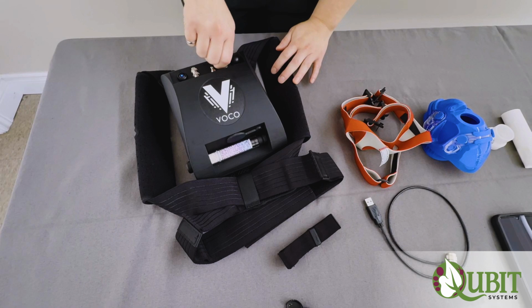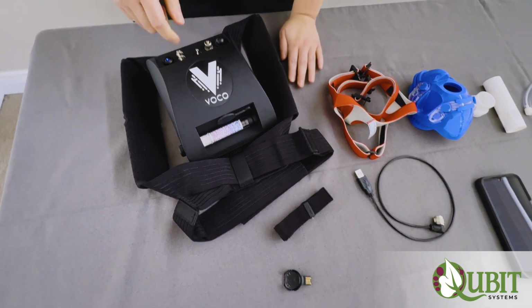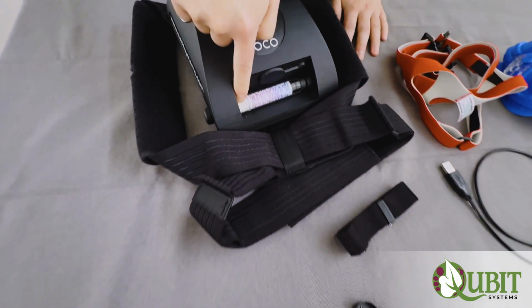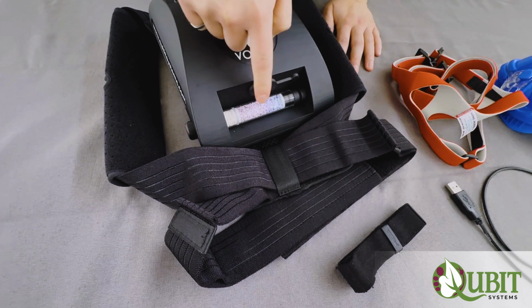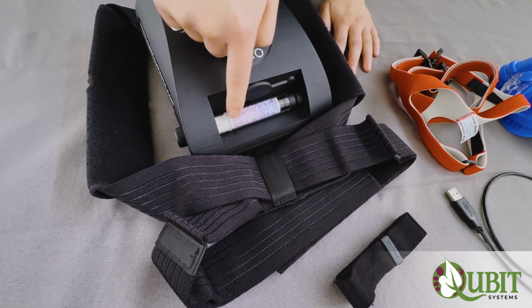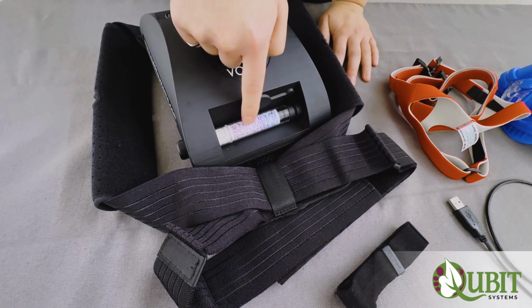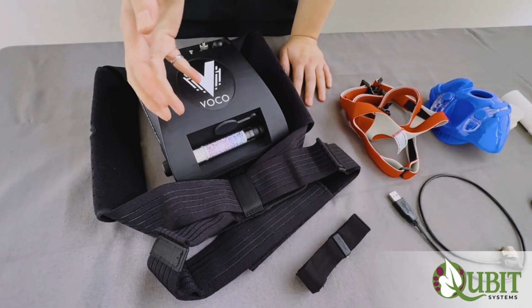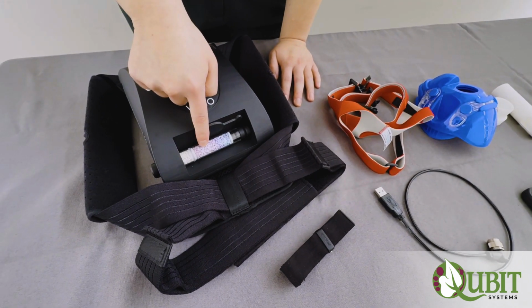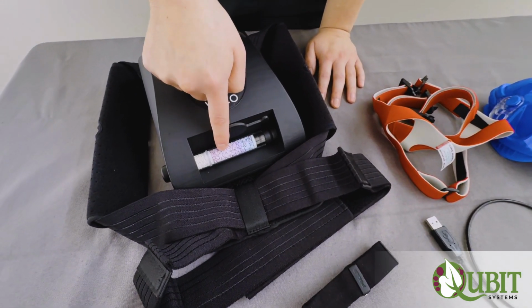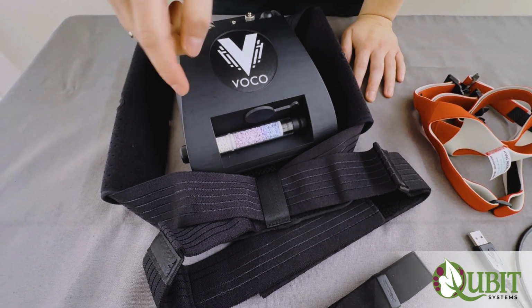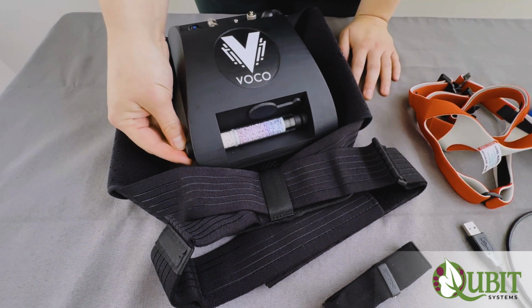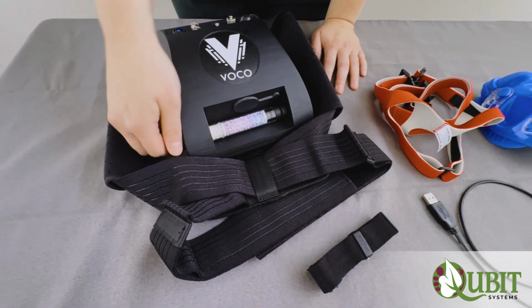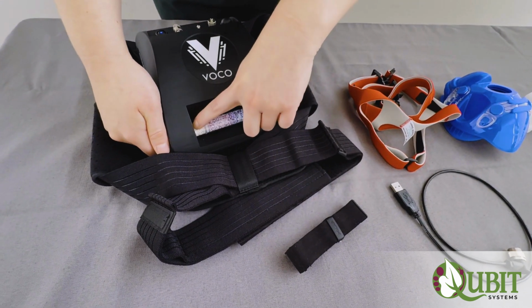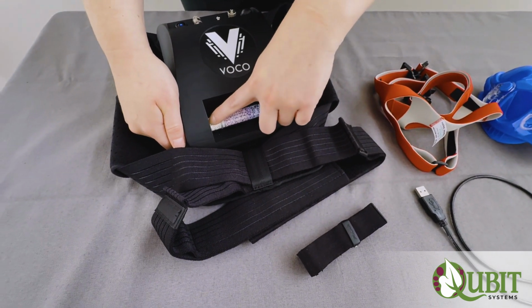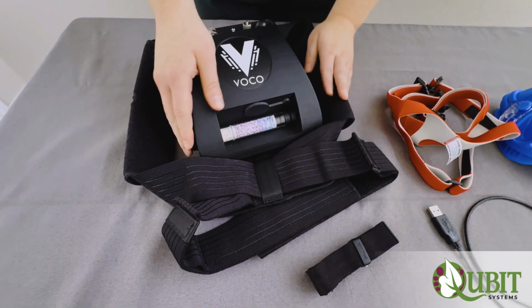Another thing to check before doing a test is the calibration column. You want to make sure that there is still enough chemical, which is good, to use during the test. The Drierite should be mostly blue. In this case, we would want to change the chemicals before a lengthy test. However, a brief test, 15 minutes, is probably fine. And then the soda lime as well. If this is mostly purple, then the column should be changed.